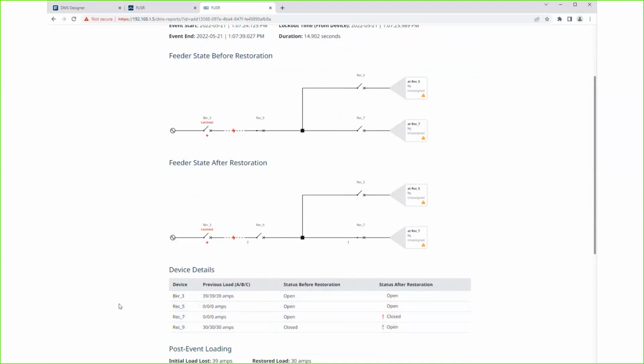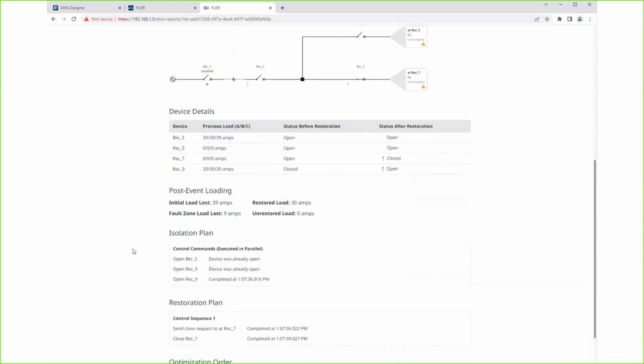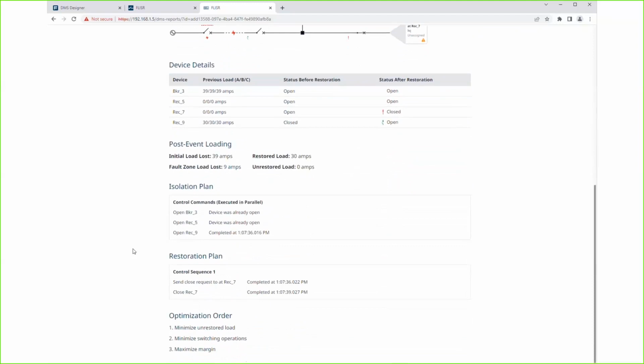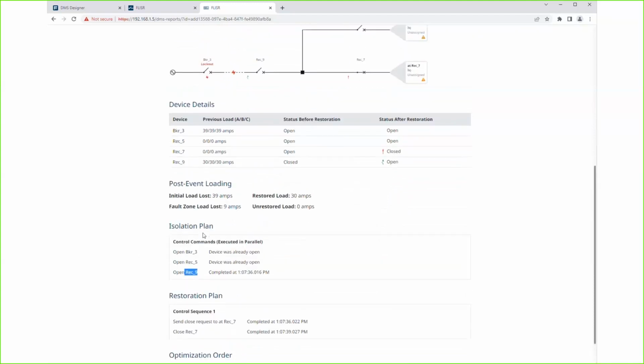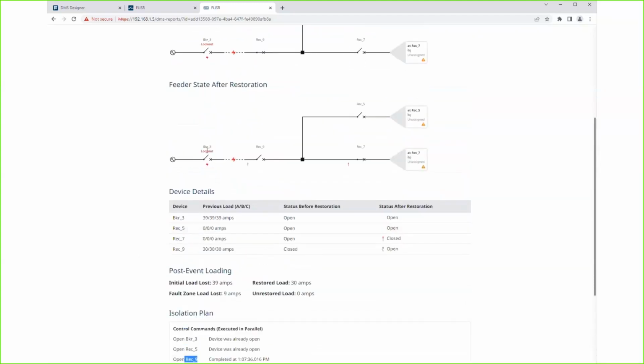You also get a table that shows you what happened. So 3-phase loading pre-fault, status before and after. We've added a lot of tool tips and data here. The objective is you should be able to make intuitive sense of what this control system saw and did. So what did it do to isolate? It opened recloser 9, and it ensured that breaker 3 and 5 were already open.